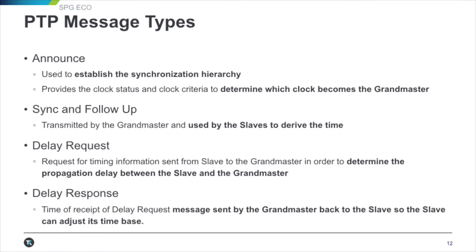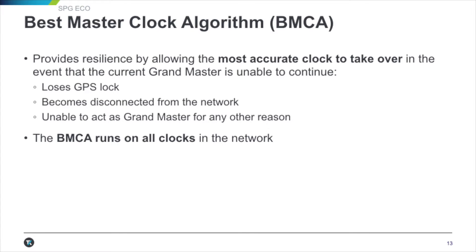Sync and follow-up is how the slaves determine their time from what is being sent from the grandmaster. The delay request is how the grandmaster determines propagation delay between the slave and the grandmaster, then sends back a delay response so the slave can adjust its internal time base. The best master clock algorithm — BMCA — determines which clock is the most accurate and which would be secondary, ready to take over if there's a loss of GPS lock or the grandmaster is unable to perform its duties. The BMCA runs on all clocks within the network because all clocks should be able to step in as grandmaster if needed.